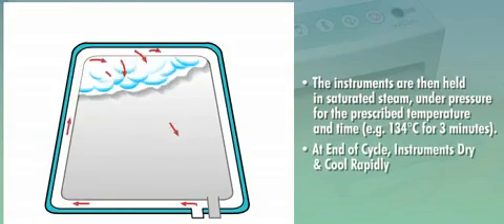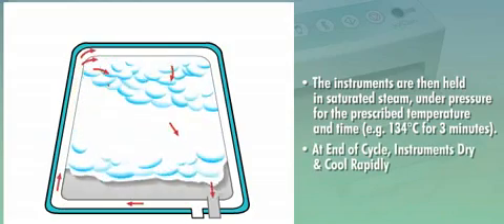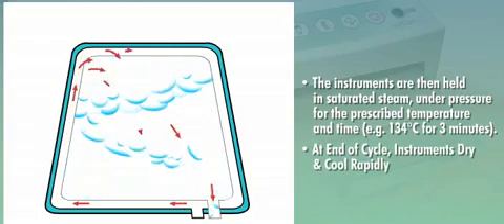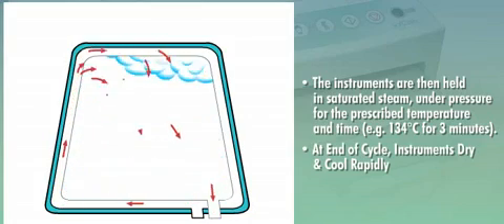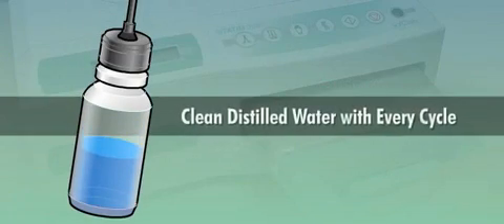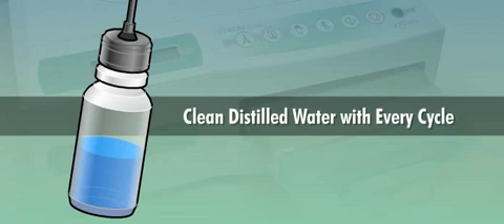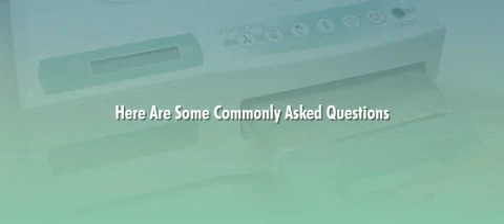At the end of each cycle, when the machine has vented, a small compressor switches on, drying and cooling the instruments rapidly. The STATIM cassette autoclaves use clean distilled water with every cycle, preventing the buildup of handpiece lubricant and other water contaminants. Here are some commonly asked questions.